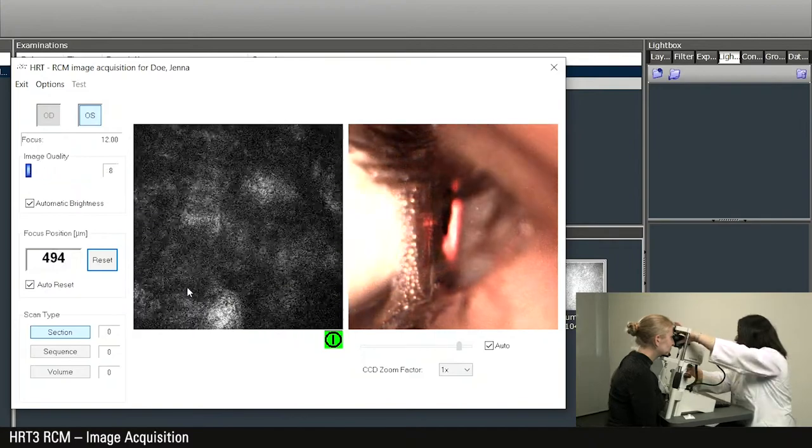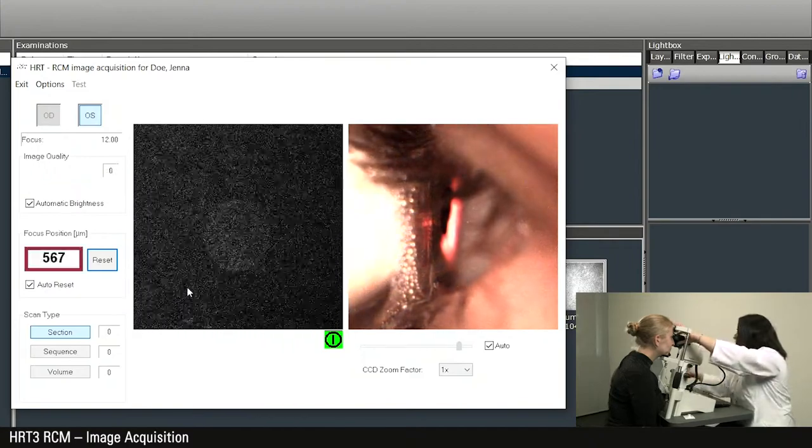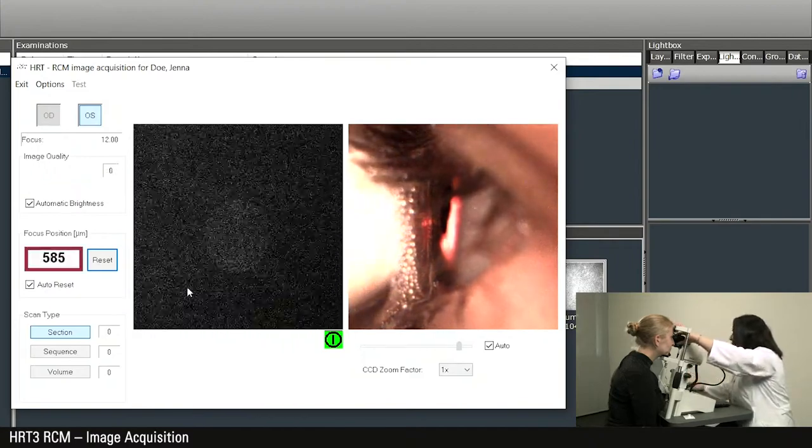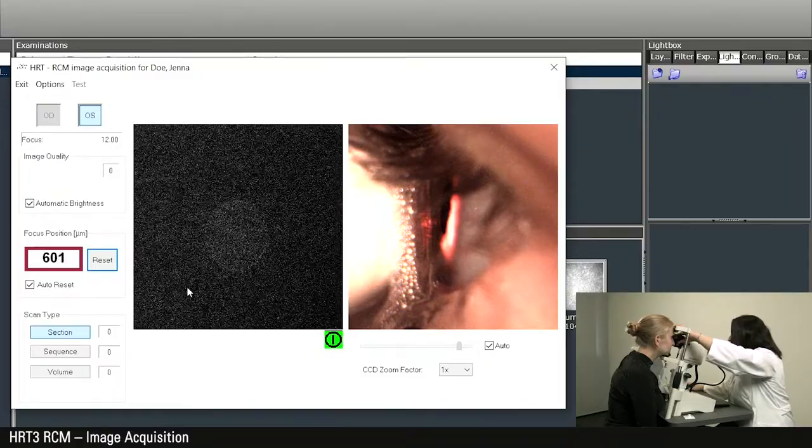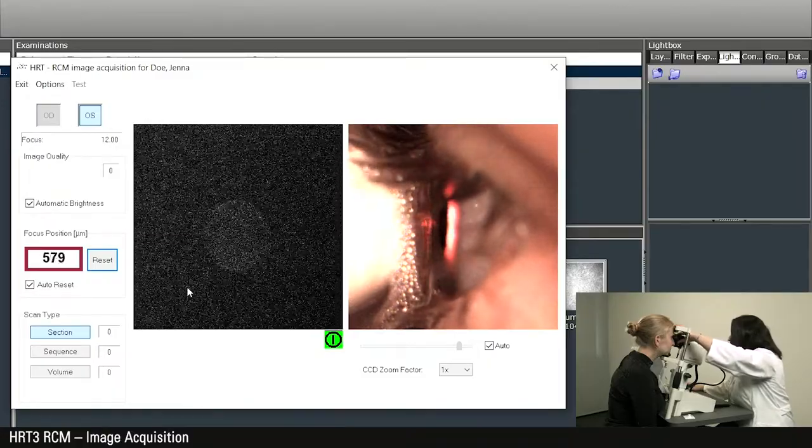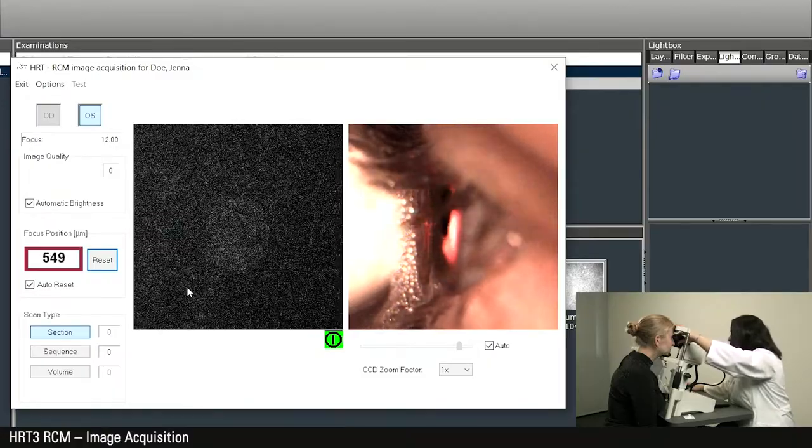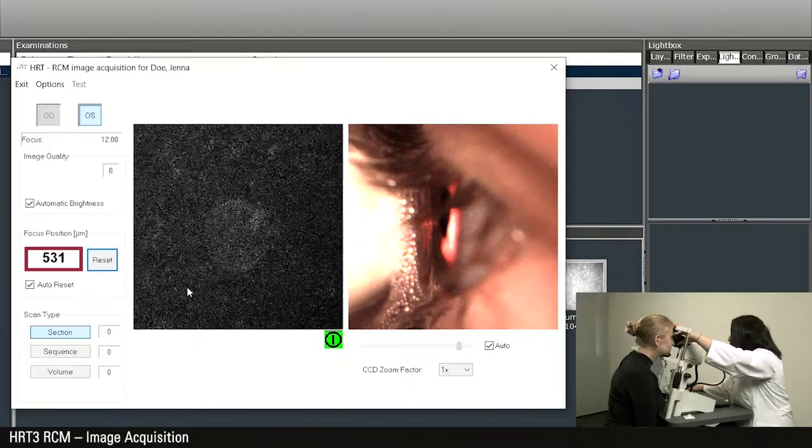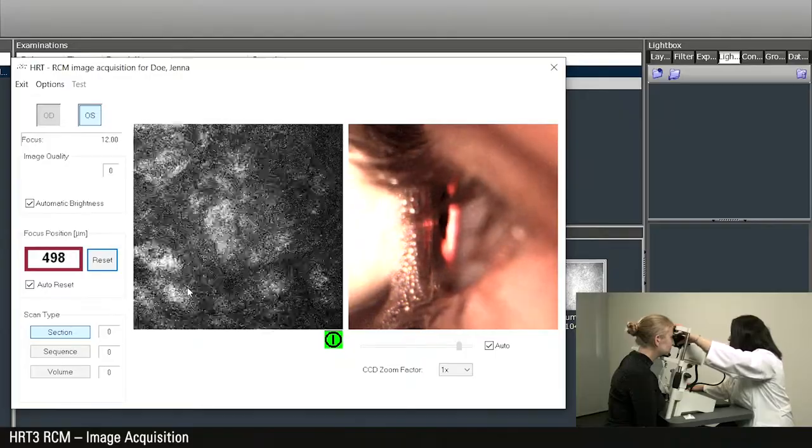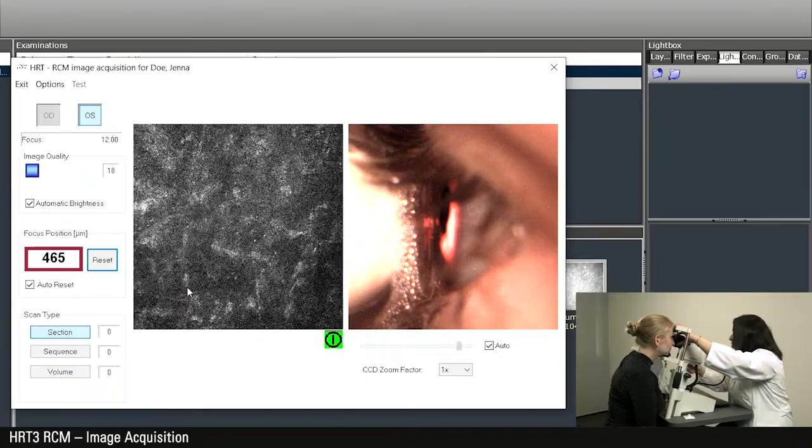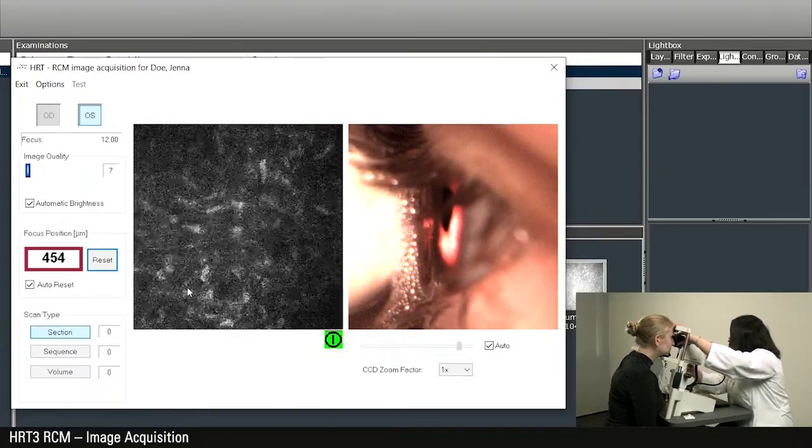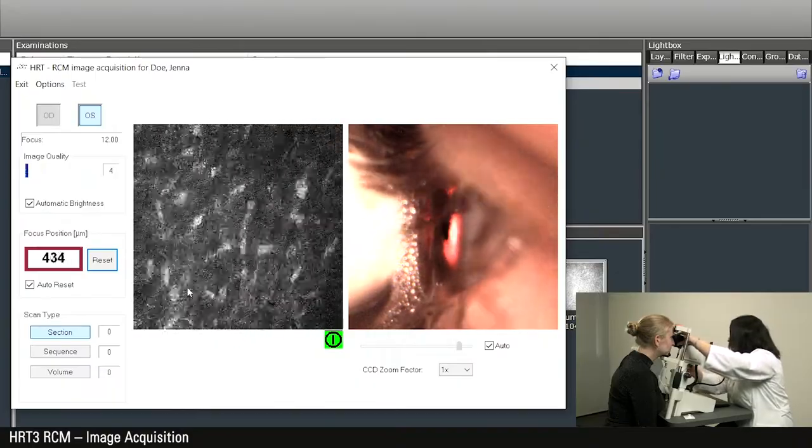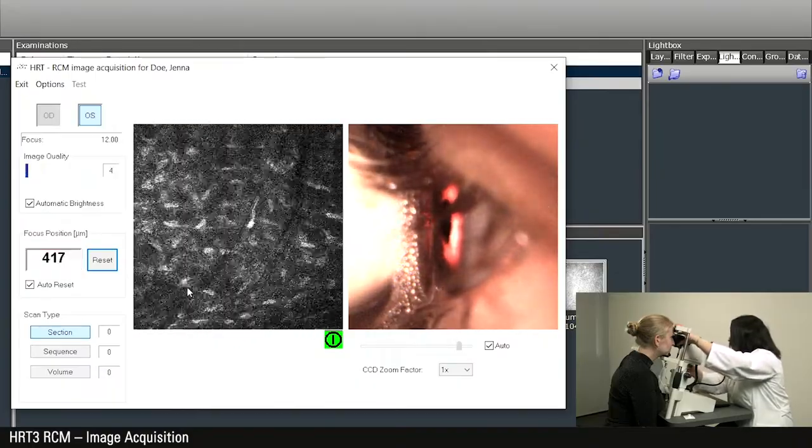Another tip is if you find yourself with a focal plane outside the corneal thickness, please turn the objective wheel back to a focal plane that is inside the corneal thickness. In case you don't get an image at all, consider applying some more gel to the eye of the patient to improve the image quality.